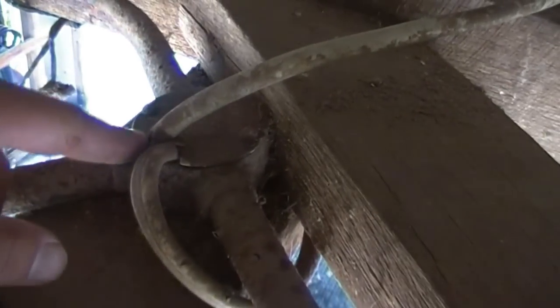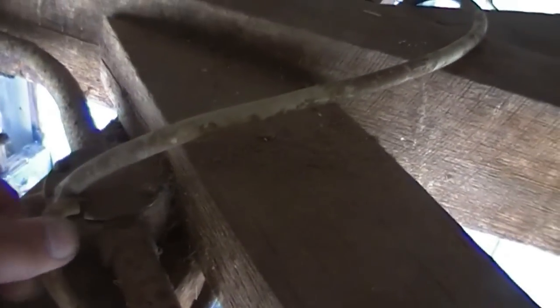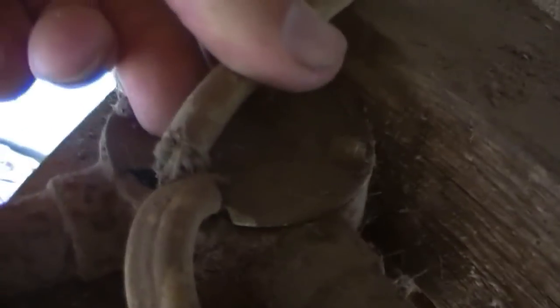Just thought I'd show you this. It is a junction box for the old steel conduit, which on its own is very dodgy stuff. But then people do this sort of thing — cut a hole inside the J-box and stick wires in there. By the looks of it there's a bare cable there, which is probably the earth. So that light over there has no earth — lovely and safe. Also, this would wear out and make this all live, so anyone who touched it would die. Unsafe.